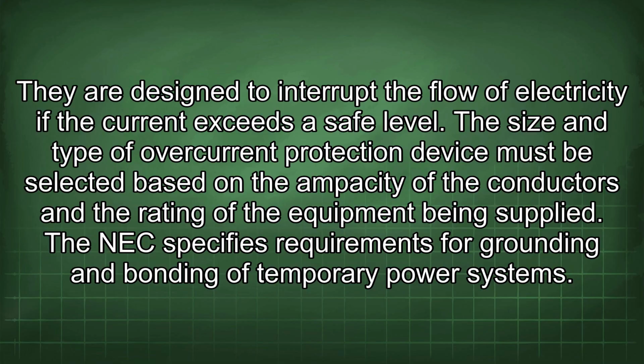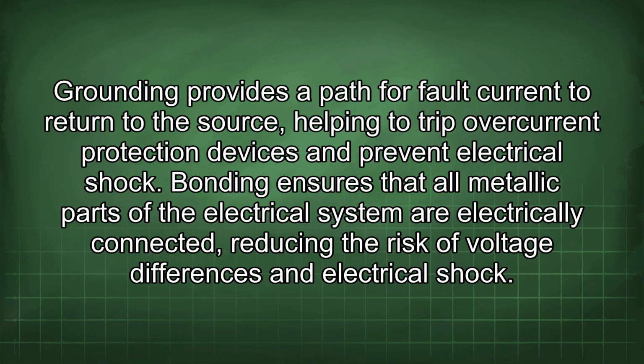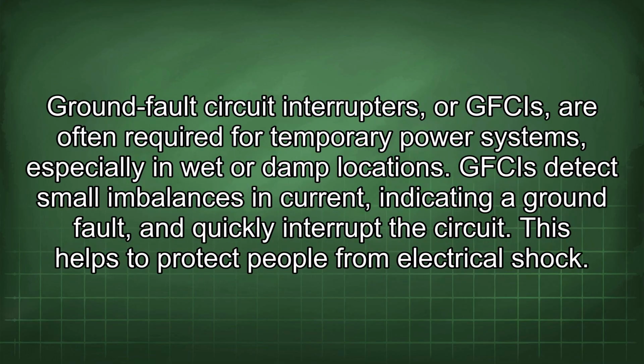The NEC specifies requirements for grounding and bonding of temporary power systems. Grounding provides a path for fault current to return to the source, helping to trip overcurrent protection devices and prevent electrical shock. Bonding ensures that all metallic parts of the electrical system are electrically connected, reducing the risk of voltage differences and electrical shock. Ground fault circuit interrupters, or GFCIs, are often required for temporary power systems, especially in wet or damp locations. GFCIs detect small imbalances in current, indicating a ground fault, and quickly interrupt the circuit. This helps to protect people from electrical shock.